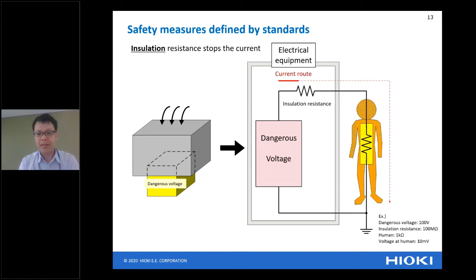So safety measures are defined by standard. How do we check these two countermeasures? For ground, we can measure using the ground bond test. For insulation, we can measure with the Hipot test, the insulation resistance test, and the leakage current test. So these four measurements are very important for checking the safety of electrical instruments: the ground and the insulation.